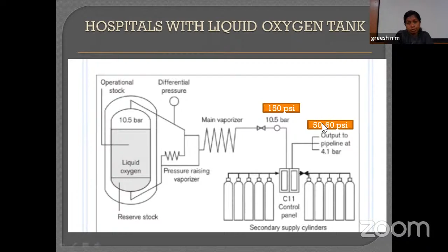1 liter of liquid oxygen will generate around 860 liters of gaseous oxygen. If the gaseous oxygen coming via the pipelines enters the manifold, the pressure maintained in the pipelines will be around 150 psi, which equals around 10 bars. From the manifold, the oxygen will enter the pipelines to be delivered to the patients, and in these pipelines the pressure will be maintained between 50 to 60 psi.